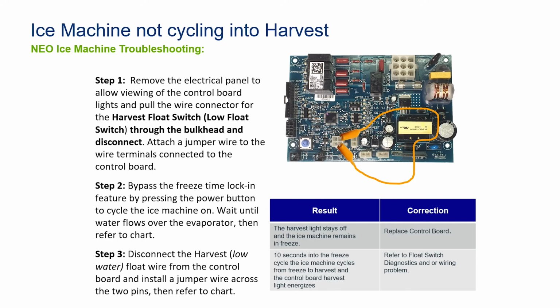But what if we still don't go into harvest? Just told you we got the float out of there, but we didn't get the harness out of there. What we would do is go straight to the control board and find what wires from the float go into the board, put a jumper there and tell the board exactly what we need to do. This one's a little bit hard to do.